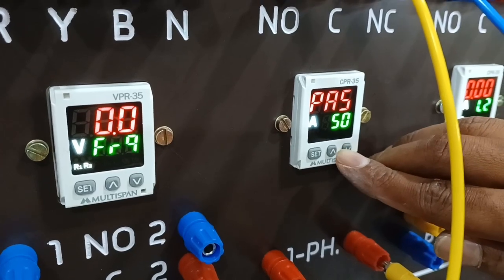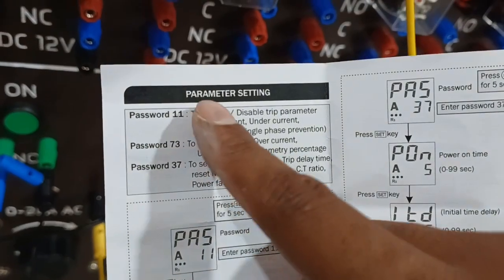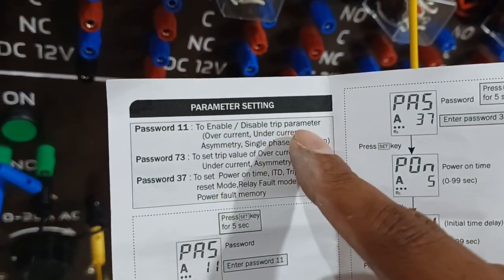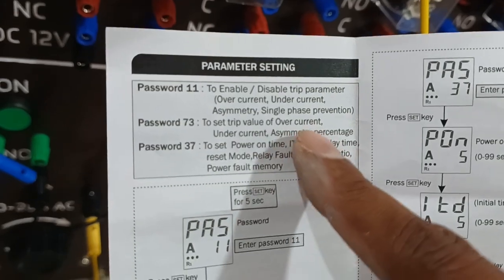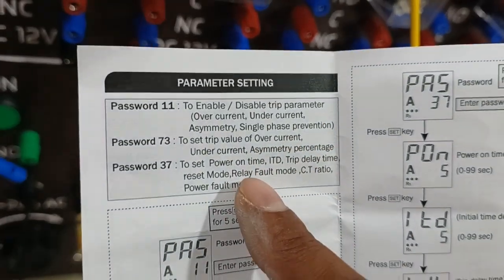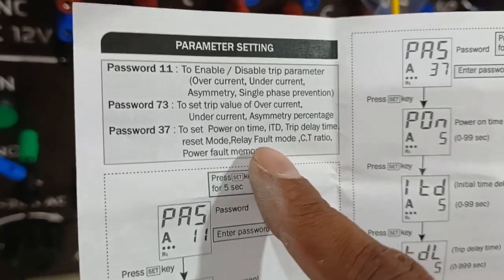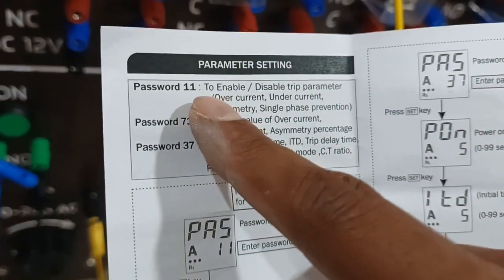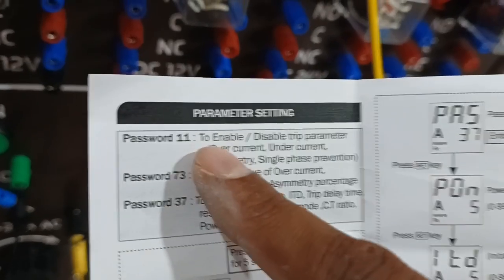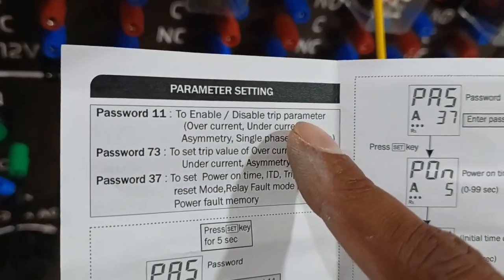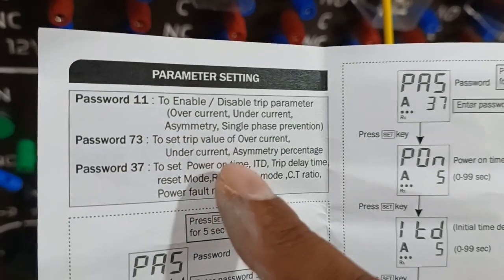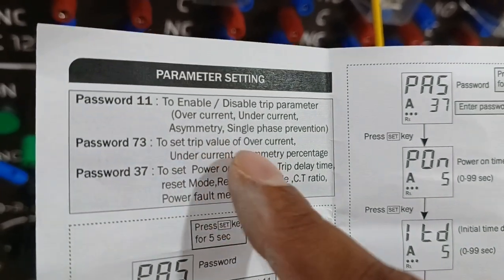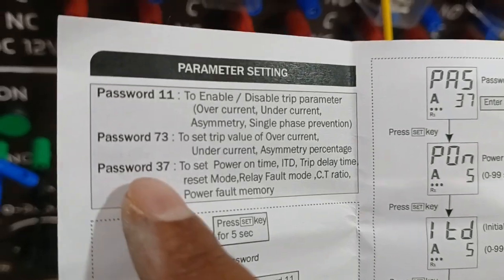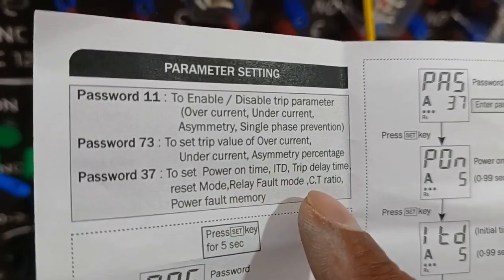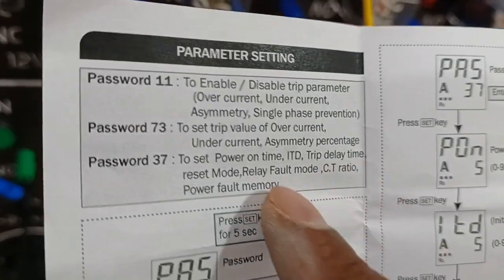And they have provided a menu like this, and here there are 3 different menus. First one is relay trip parameter menu, second one is protection menu, and third one is trip CT ratio and trip setting menu. For each menu, they have provided password protection: password 11 for relay trip parameter settings, password 73 for relay trip percentage setting, and password 37 is for CT ratio and trip time delay settings.